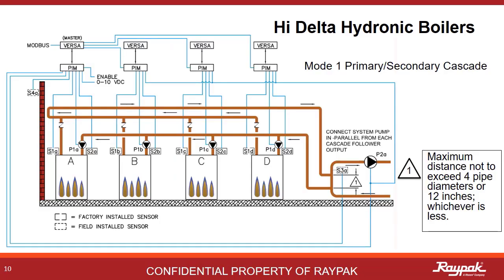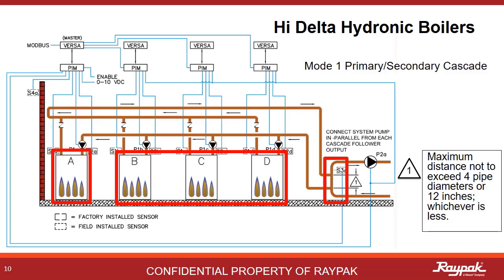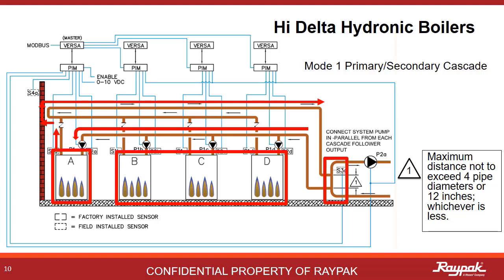This is the Mode 1 cascade system. Boiler A on the left is the master boiler, and boilers B, C, and D are the followers. All of the same decoupler concepts apply — only now they apply to the whole cascade. An important part of plumbing boilers in cascade is to use reverse-return logic: the first boiler out to the loop is the last boiler to receive water back from the loop.